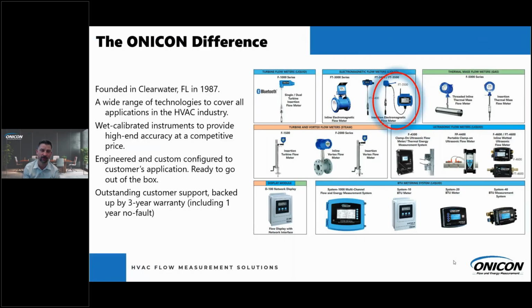In all of our flow meters, we build and calibrate to the specific application. So you tell me you have a 6-inch pipe, chilled water, average flow is 500 GPM. We build that flow meter, physically put it in a 6-inch pipe and give it a wet calibration, and it'll come with a calibration certificate for that specific application. I like to tell all the installing contractors, this flow meter was built, calibrated, and factory programmed to that application. So the 10-minute rule: if you can't get the flow meter working in the first 10 minutes, stop what you're doing, call our rep or call our factory, and let's figure this out, because it should be ready to go out of the box.